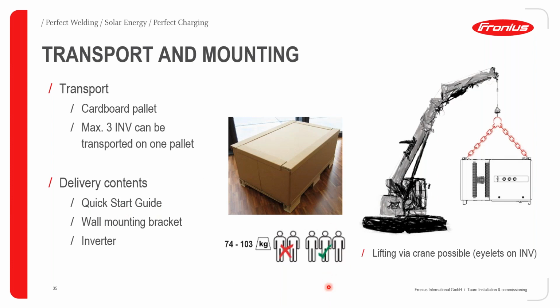So the Tauro is a heavy inverter. If you're looking at the 50 kilowatt Tauro, it's 74 kilograms, and the 100 kilowatt Tauro is 103 kilograms. So again, we suggest that you use at least 3 people to lift this inverter. Also, what's really cool with the inverter is that you can use a crane to lift it. So maybe, I don't know, you need to lift the inverter to the top of the ceiling. What is provided on the Tauro is that we do provide you with eyelets. So you can see it here on the left and on the right.